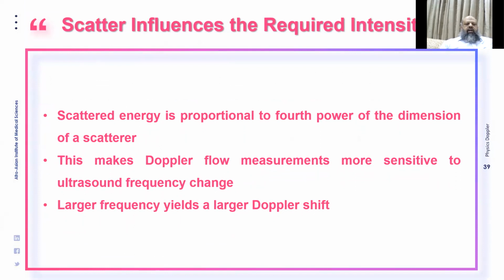Something about scattered influences and the required intensity: the scattered energy is proportional to the fourth power of the dimension of the scatterer. This makes Doppler flow measurements more sensitive to ultrasound frequency change. A larger frequency yields a larger Doppler shift.